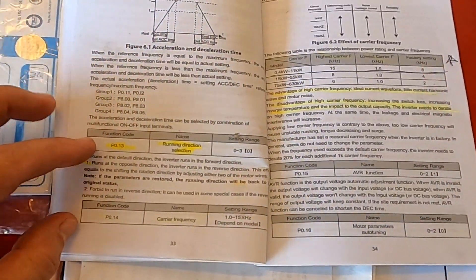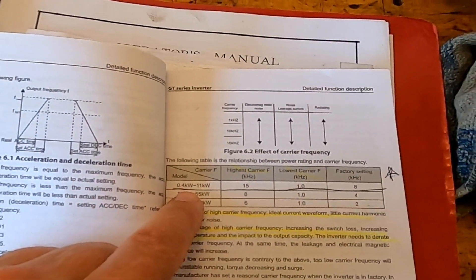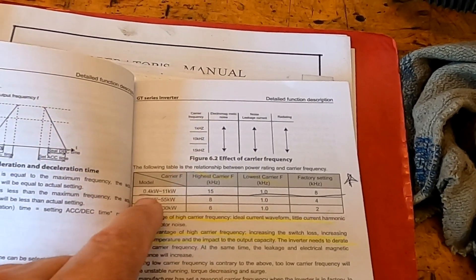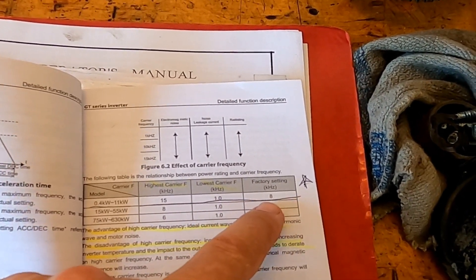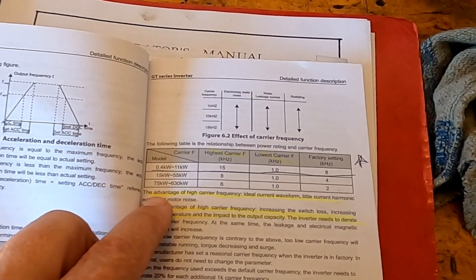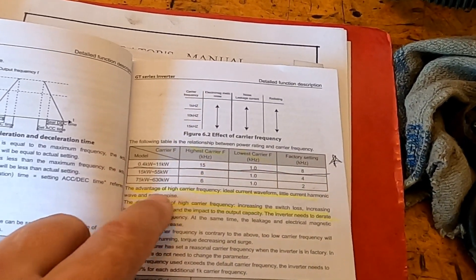Before we get going on this, we need to find a carrier frequency, which is right here on P014. So let's read up about carrier frequency. We're running a seven-and-a-half horsepower motor, so that's about 5.5 kW. If we look in the chart here, the highest carrier frequency we can use is 15. It's supposed to be set on 8 at the factory. It sounds a lot louder than my last one was on the factory setting. The advantage of high carrier frequency is ideal current waveform, little current harmonic wave, and reduced motor noise — so basically by changing your carrier frequency you can change the pitch of the motor noise.